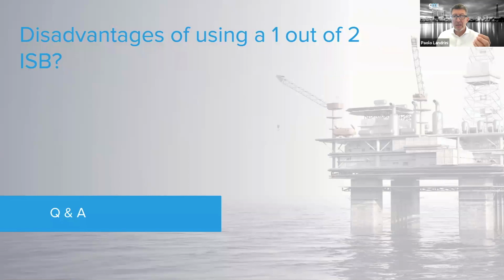They say, if I have a Zener barrier, can I replace it with an isolated barrier? Yes, this is more easy than the other way around, because an isolated barrier does not require grounding, so you don't need to connect to ground. And this answers another question: can they be connected to the same ground? No, because the isolated barrier does not require grounding, as we saw earlier.